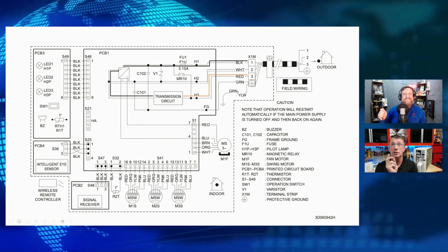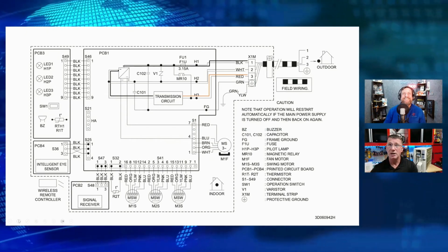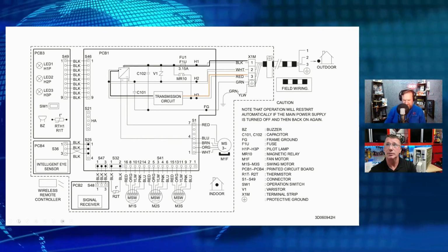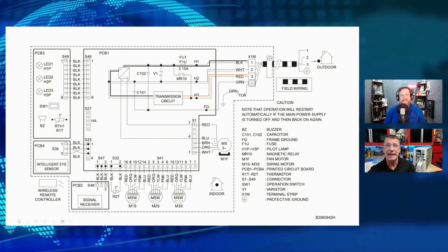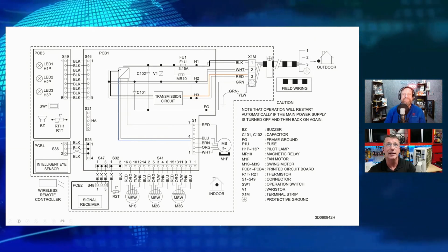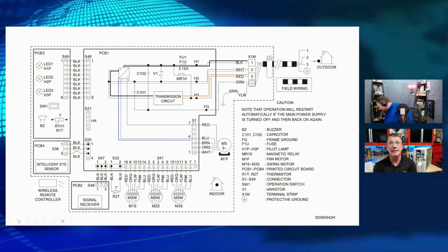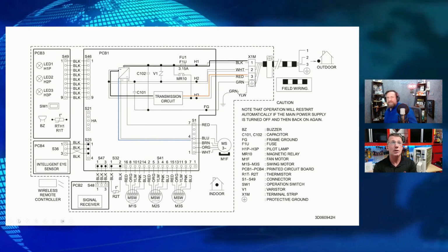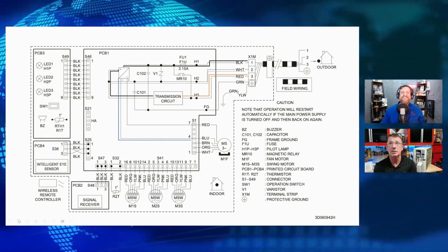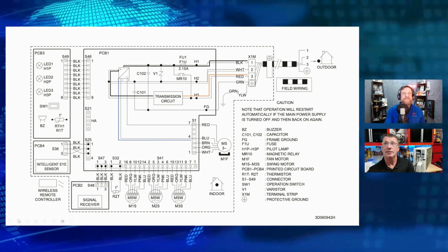And I'm going to show you what it looks like on a 120 and a 240. So we're going to share a communication circuit, but we're going to have AC and DC all traveling on these 3 wires. And we'll prove that here in just a minute. So on that indoor control board, if I've got DC that is going to be running the indoor fan motor and running my thermistors, I'm actually just going to come off from that voltage rectifier.